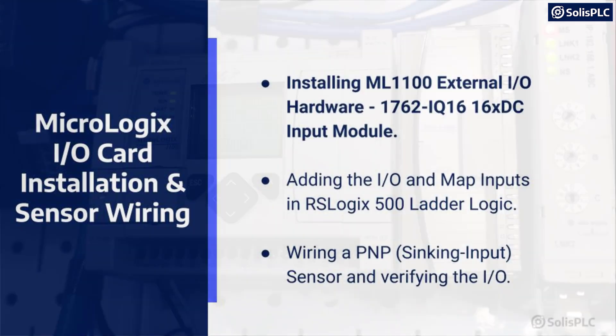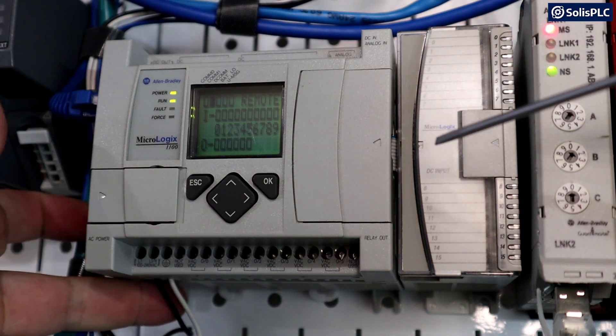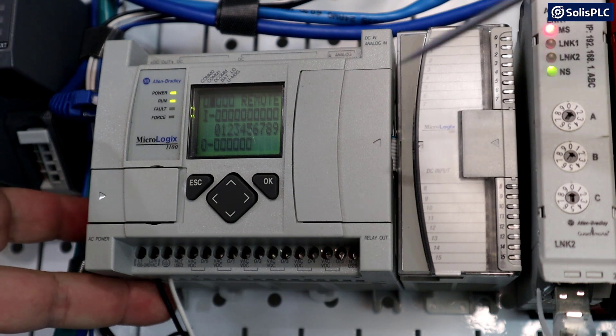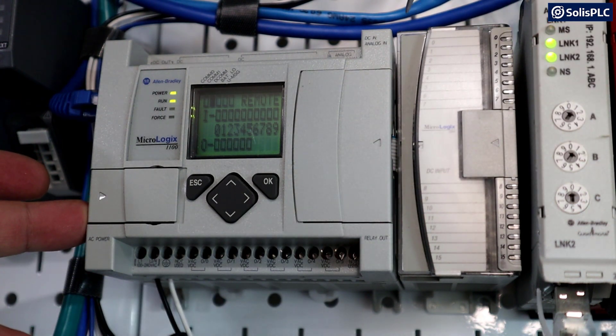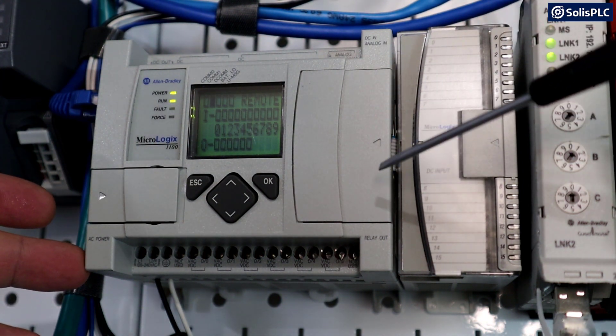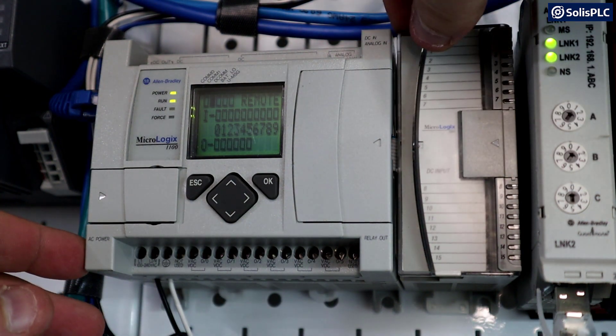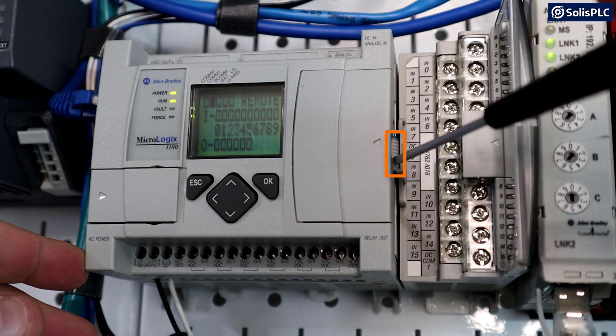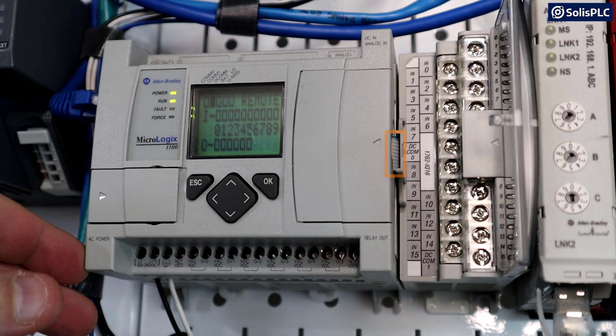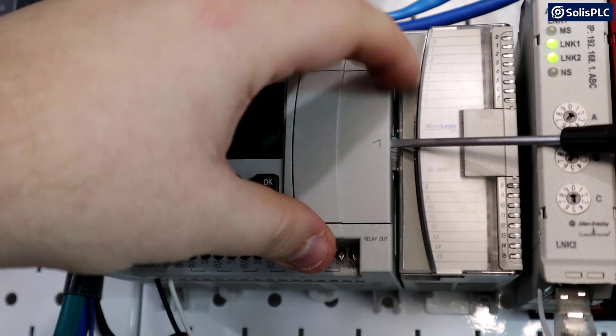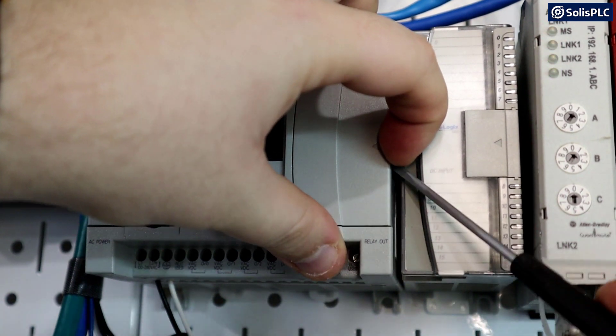Okay, so here we've got the MicroLogix 1100 series. It is currently connected over Ethernet and powered over 110 VAC. What I'm going to be doing is live, but I do recommend that you shut down your PLC when you're performing this operation and connecting the I/O. Once you get this card, you'll notice that on the left hand side there's going to be a ribbon cable that's sticking out and that is where it's going to connect to the MicroLogix series. I'm just going to close this little door and use a screwdriver, a flathead, to pry that door open. It does give you a little bit of a hard time when opening it with the connection already in place.